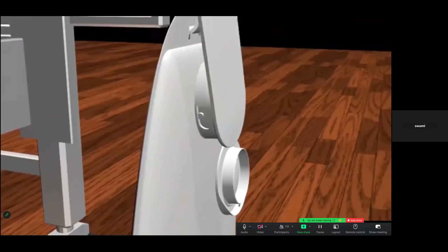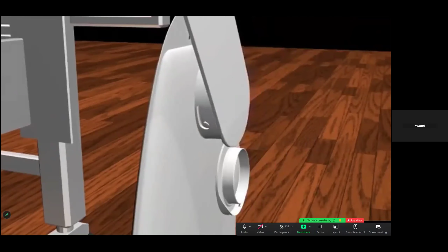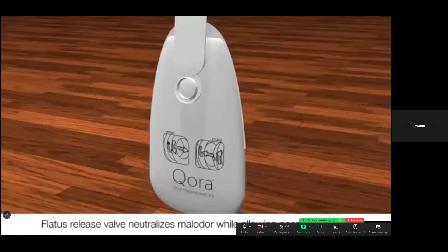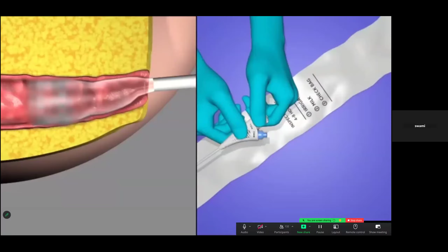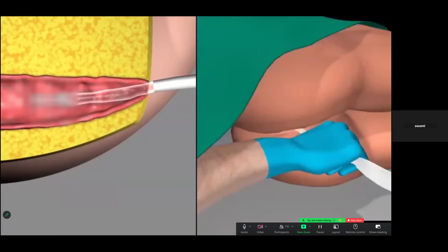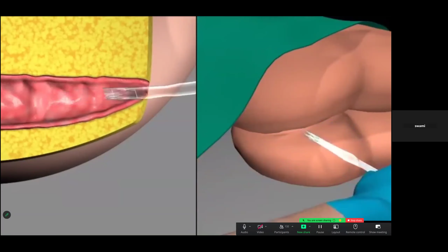To exchange the bag, disengage the collection bag by carefully rotating the bag connector counterclockwise from the transit sheath connector. To add a fresh bag, mate the collection bag connector to the transit sheath connector and rotate clockwise until they lock together. The bag is provided with a flatulence release filter to prevent ballooning. To withdraw the device, firmly hold the Y connector with your hand and use your dominant hand to pull the white cap towards yourself until the white tether is taut. The indwelling diverter is now collapsed in the rectum. Slowly retrieve the device by holding the transit sheath close to the anatomy. Dispose the device according to institutional protocol.